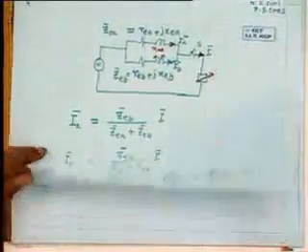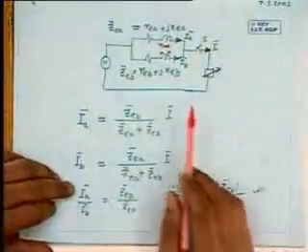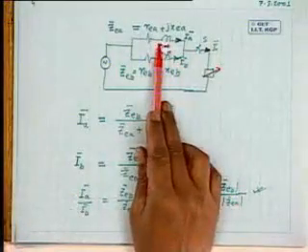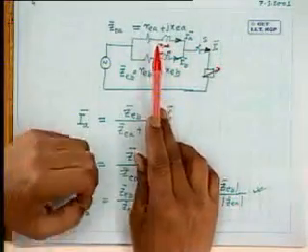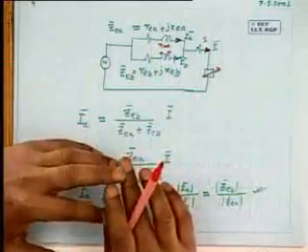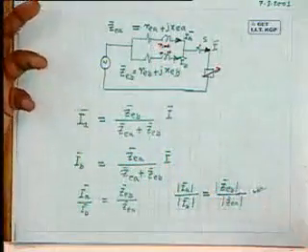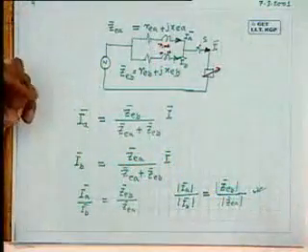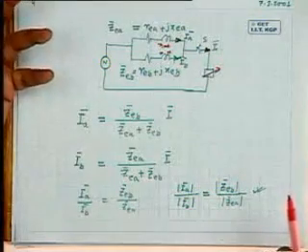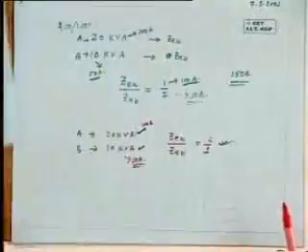So with two transformers of impedances of this type, when transformer B carries 50 ampere, transformer A carries 25 ampere. That is, transformer B is fully loaded, but transformer A remains underutilized. Further loading is meaningless, because you can load further, but then transformer B will become overloaded.